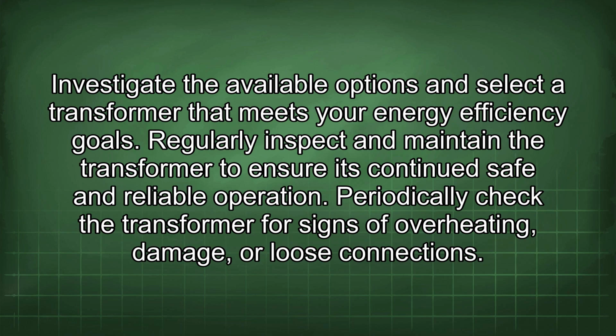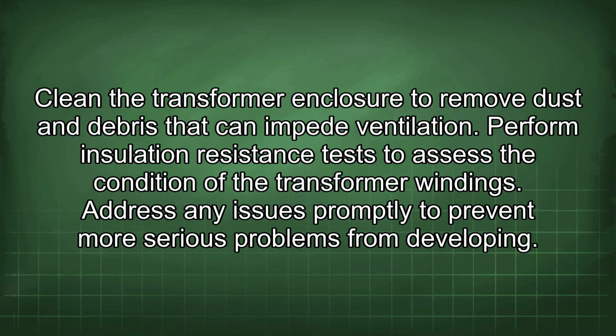Regularly inspect and maintain the transformer to ensure its continued safe and reliable operation. Periodically check the transformer for signs of overheating, damage, or loose connections. Clean the transformer enclosure to remove dust and debris that can impede ventilation. Perform insulation resistance tests to assess the condition of the transformer windings. Address any issues promptly to prevent more serious problems from developing.